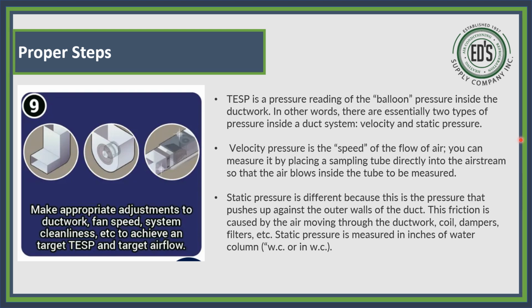Now, if you get to where you're going too big, you let too much airflow come through, you're going to cause another effect that we'll get into later. But the TESP is a pressure reading of the balloon pressure inside the ductwork. Now velocity pressure is the speed of the airflow. So velocity is the speed of the flow of air, and you can measure it by placing a sampling tube, which was the other piece in that dual manometer. There is a clear tube with a black fitting. You can put that in the ductwork, and that will get directly into the airstream, and that will let the air blowing inside the tube be measured.